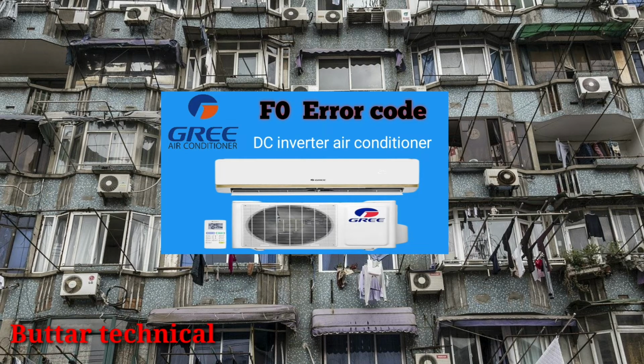Number 3. Check the control board for any signs of damage or burn marks and replace it if necessary. Number 4. Check the temperature and humidity sensors on the indoor and outdoor units and replace them if necessary.